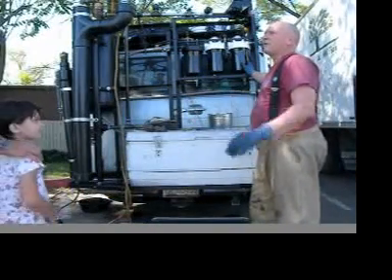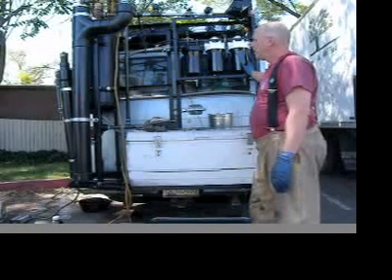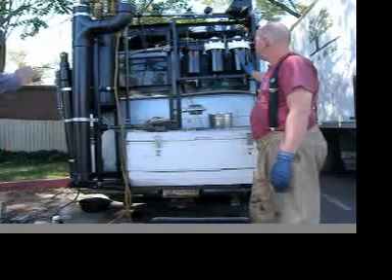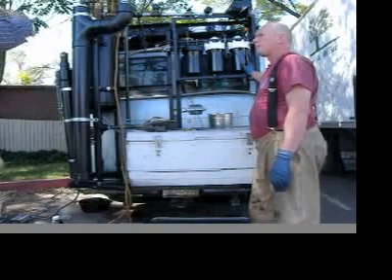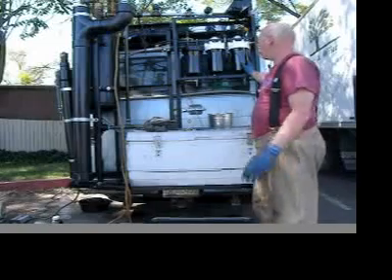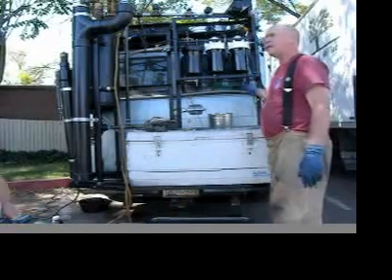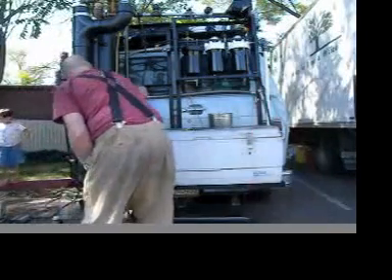That says the filter is plugging up. That would normally be your indication of when the filter needs to be replaced — when you're having to apply some pressure. If I backflush my filters with these valves, that's the signal it's time to backflush.